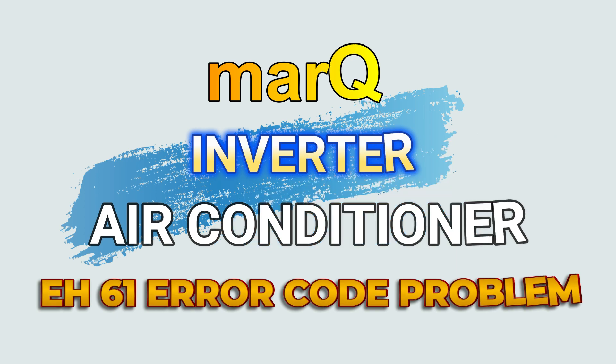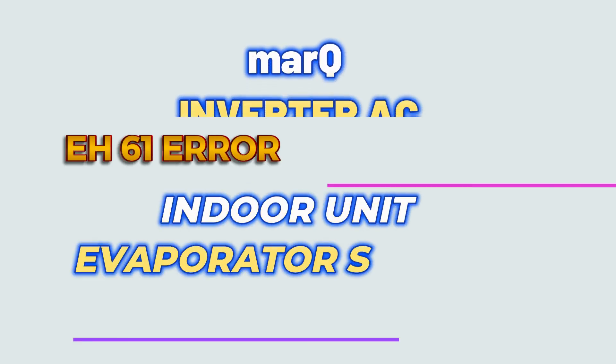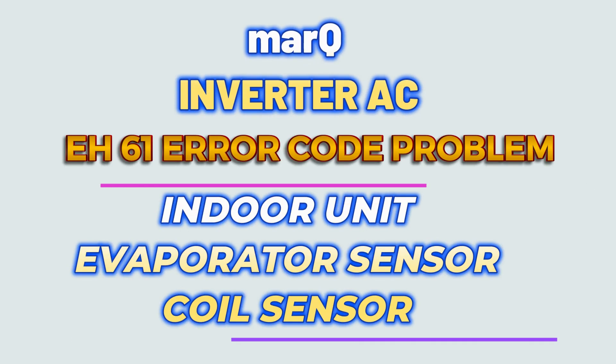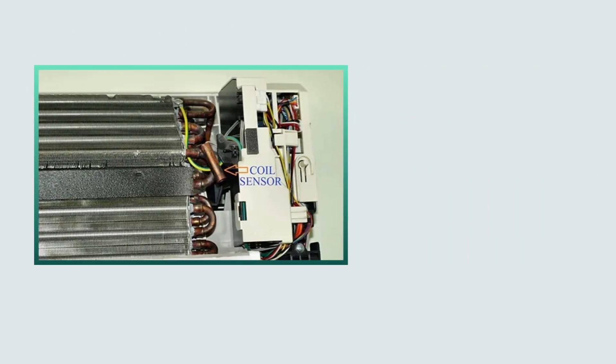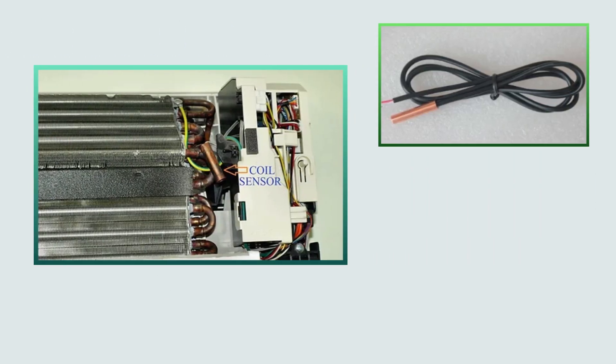If EH61 is coming in marQ AC, then it is the error of evaporator sensor. In simple words, it can be called coil sensor. This sensor is installed in the coil of the indoor unit.